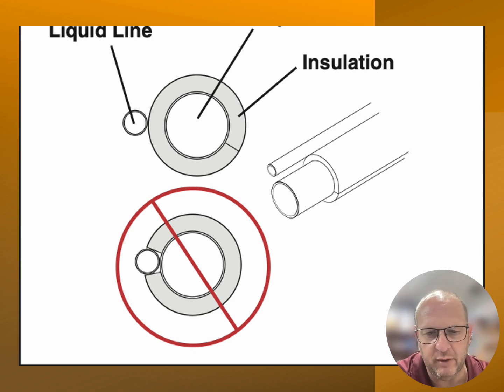Now, if you do have a line set that's coming to you, you want to make sure that when you go to insulate it, you are separating out the liquid line and the suction line. Never run that insulation around it so that the liquid line is touching that suction line. That is not the correct way to install the suction line insulation. Remember, our suction line will sweat because it's below the dew point of the air. It's cold and it's going to condensate, so that's why we need to insulate it.